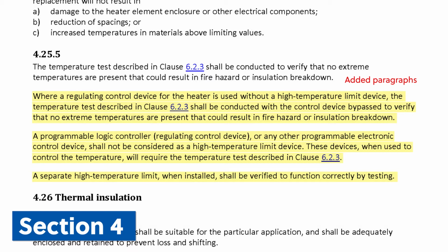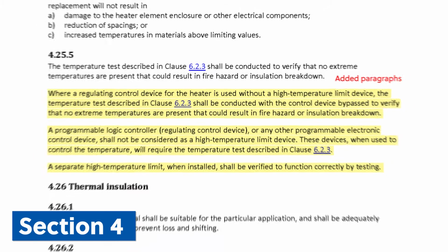What this very clearly means is that it's expected that as part of temperature testing, a high temperature limit is tested. Practically speaking, you would have to ask your customer's permission before operating equipment to the point where the high temperature switch is tripped.